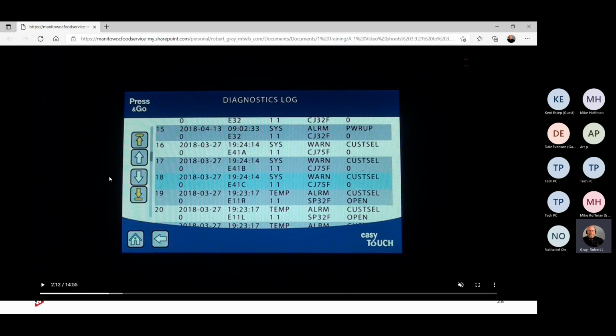One of the transformers has taken the input AC voltage down to low voltage to go through the communication cable up to your SIB, and that is probably going to be the problem. Okay, so it gives you that heads up. Well, I just described that. Chances are if you have a 41A, B, or C, end result, it could be the solid state relay board.